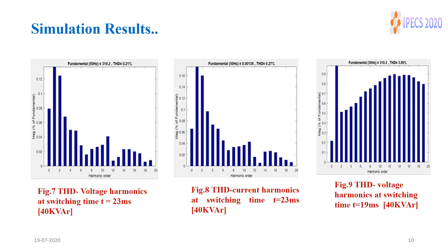And when we go to figure 9, it is the THD for voltage harmonics where the switching time is now reduced to 19 millisecond. So what happened? The capacitor bank is the same size, 40 kVAR. Now we see a little increase in the THD value. This is 3.90% for the voltage harmonics. So this effect is because we reduced the switching time.